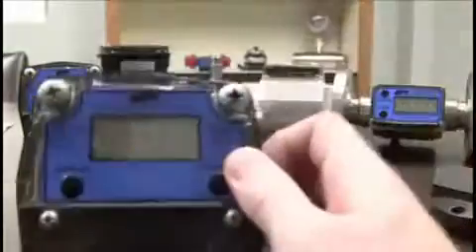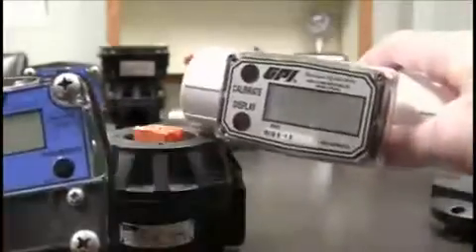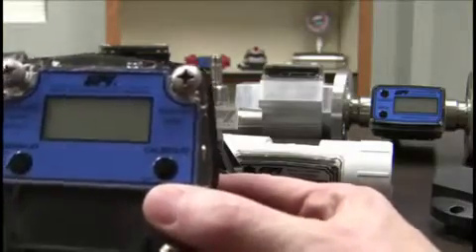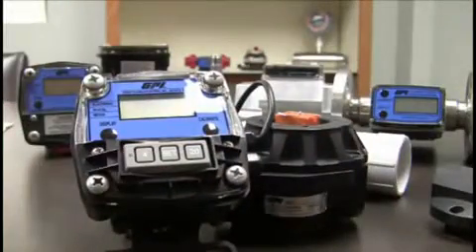So it's going to look just like that. The display can sit on top, just a regular GPI display on there. And it's going to do the same thing. It's going to count those pulses. The display knows exactly how many pulses equals a gallon just the exact same way the turbine meter does. And so then you can see what you've got on there. Also you can send out 4 to 20 milliamp signals or pulses. Here's one that has a 4 to 20 milliamp signal. You've got your four set and 20 buttons to get that working.